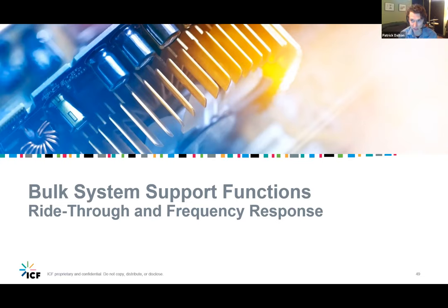And I have seen some research by EPRI and others showing that if DER VoltVAR settings aren't properly coordinated with utility voltage regulation settings, the DER can actually be trying to control voltage for the entire feeder, and it could prevent load tap changers, or more likely a midline voltage regulator, from controlling voltage. So the DER just keeps on absorbing more and more reactive power up to the limit, and that may suppress the voltage enough to stop a load tap changer or a voltage regulator from operating. But that's probably not what we want from a system perspective, because all of that reactive power is creating losses.